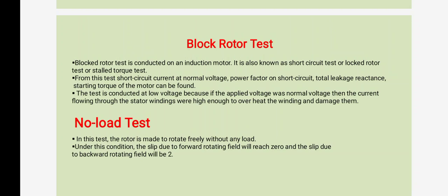This test is conducted at low voltage because if the applied voltage were normal voltage, then the current flowing through the stator winding would be high enough to overheat the winding and damage it. So the blocked rotor test is generally called the short circuit test.